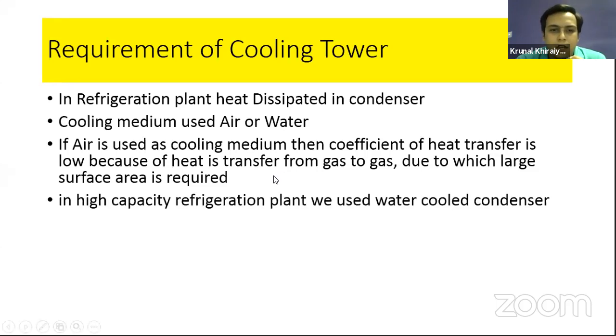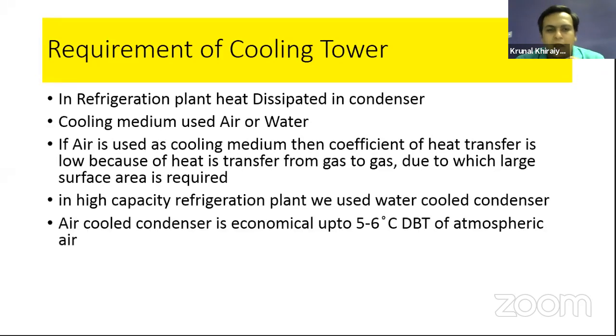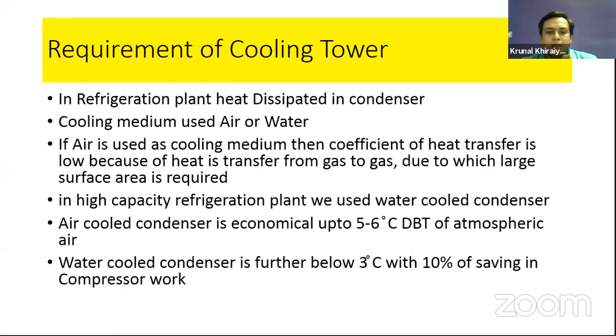Next, in high capacity refrigeration plants, we use water-cooled condensers. Air-cooled condensers are economic up to 5 to 6 degrees above the atmospheric air temperature. Meaning if you want to do heat rejection within 5 to 6 degrees of the atmospheric dry bulb temperature of air, then obviously an air-cooled condenser is very economic. But when you go lower than that, moving downward, 7 degrees below the DBT of atmospheric air, suppose 7, 8, 9, then the compressor work increases and you cannot get the efficiency. So we use water-cooled condensers, which work at 5 to 6 plus 3 degrees centigrade from the DBT, with a 10% saving in compressor work. This is the benefit we get in compression work, and it obviously affects the overall performance of a refrigeration plant.